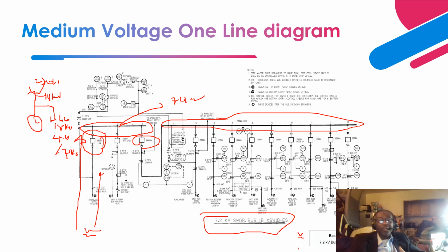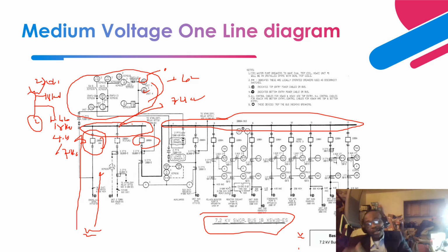So that is how the redundancy and reliability is built when you're designing switchgears. Okay, so over here is all the protective relay schemes that are part of these switchgear, medium voltage switchgear. As you can see over here, you can have under voltage relays, over voltage relays, timers, 62, right? That basically helps in terms of transferring of power and voltage from one bus to another bus, right?